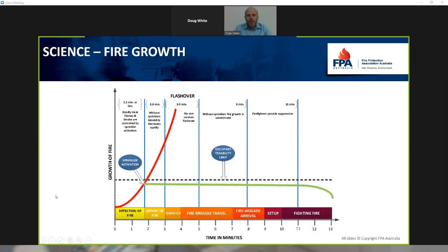This is a visual graphic representation of what we just saw. The line across the bottom here is the fire brigade expected arrival times. The red line is what the fire would do if there were no sprinklers, and the green line demonstrates what would happen from a tenability point of view when there are sprinklers. I'm probably preaching to the choir here, but it's an important point that once the sprinklers activate early in a fire, we can control that fire and achieve the objective, which is not to protect the building, but to get the occupants out of the building.